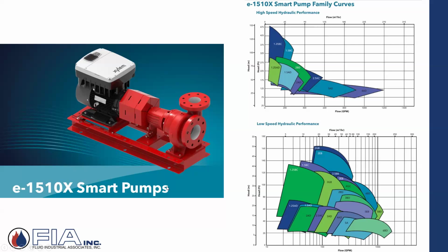They get into some pretty aggressive speed control, and they'll reference it in their pump curve performance charts. They'll say high speed, and then they have a family of low speed. What they're referring to in RPMs, traditionally, would be 3,600 and maybe 1,750 or 1,800. They might be a little bit higher, close to 4,000 RPMs on the high speed family, and then reducing down. And in the low speed hydraulic performance, it's 2,000 RPMs and below.